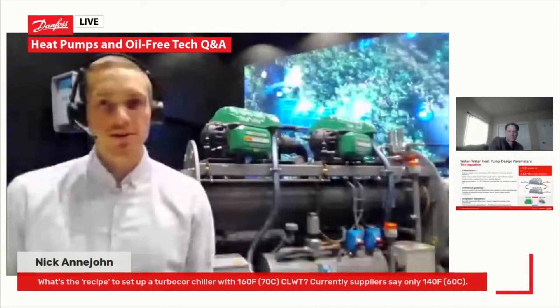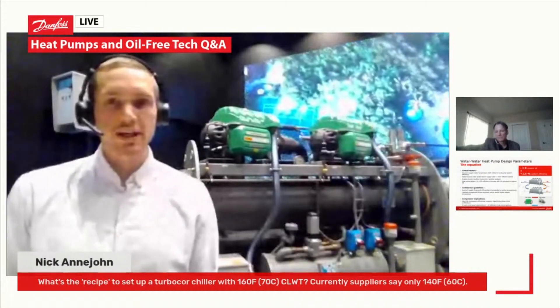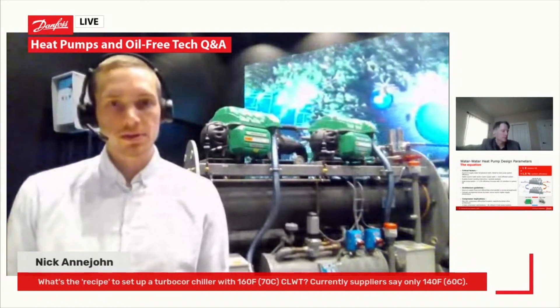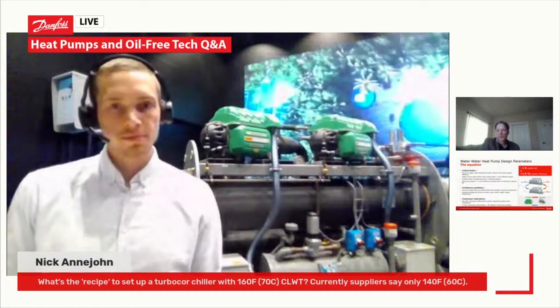Nick followed up and said they were looking at 50 Fahrenheit for the source. So with 50°F source water, you're probably coming out about 38 to 40 on the evaporator — it depends on the differential and the flow. Coming in at 50 degrees Fahrenheit, which is about 11 degrees Celsius. So that's on the lower temperature source water side.